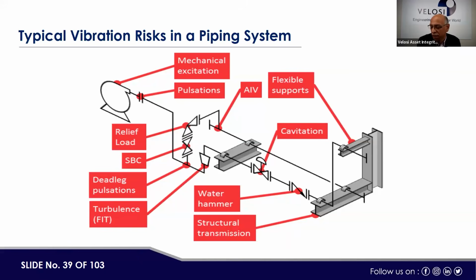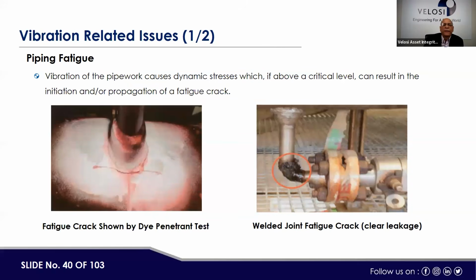So, piping fatigue due to vibration: what kind of issues are caused, and why is vibration a concern? Why do we need to make sure the vibration levels of the piping system are kept under control? Here there is one figure showing a fatigue crack revealed by a dye penetrant test. There is one crack shown here. There is also a weld joint fatigue crack, with clear leakage you can see on the side here. So this is one example of how vibration can cause failure and leakages in the system.